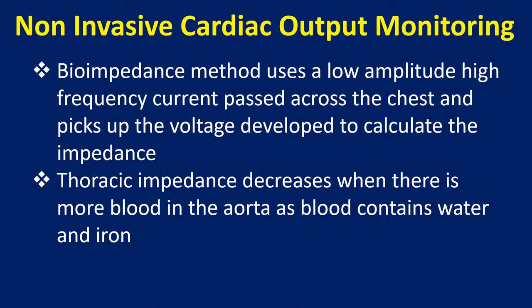The bioimpedance method uses a low amplitude, high frequency current passed across the chest and picks up the voltage developed to calculate the impedance. Thoracic impedance decreases when there is more blood in the aorta, as blood contains water and iron.